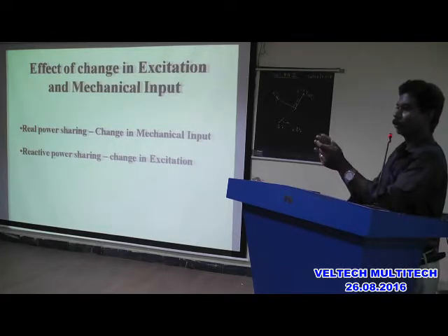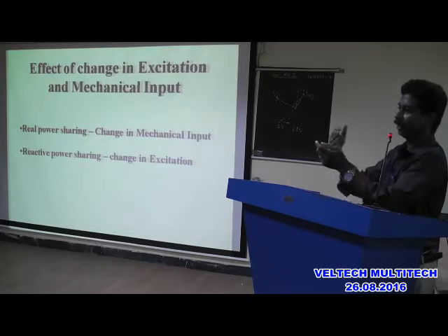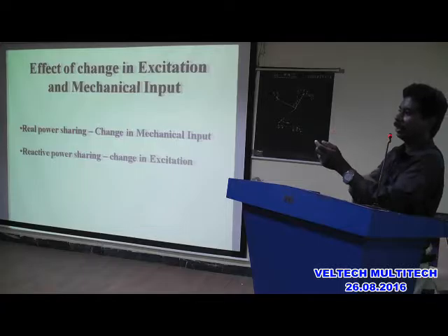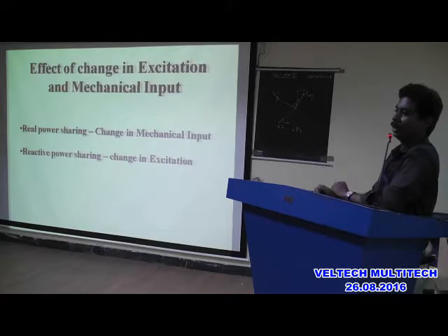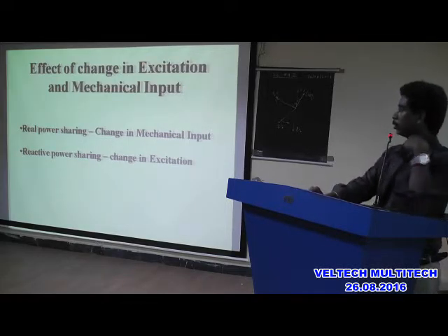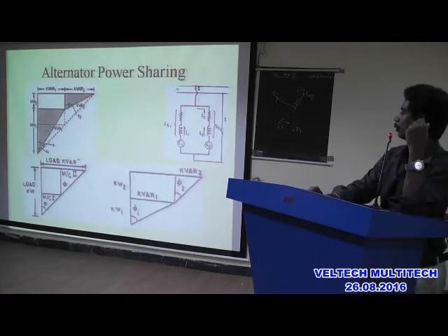Suppose you are increasing the speed of the first alternator, that is, you are increasing the mechanical input, which increases the speed. Then that particular alternator will have more real power. Suppose you are increasing one alternator's excitation, then that alternator will serve more reactive power. So you can have this idea.